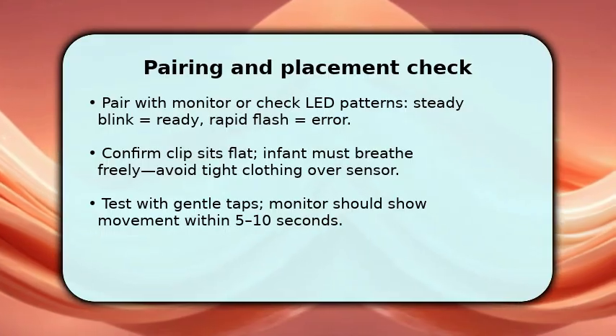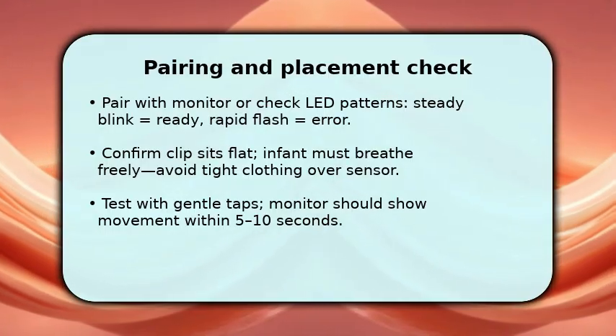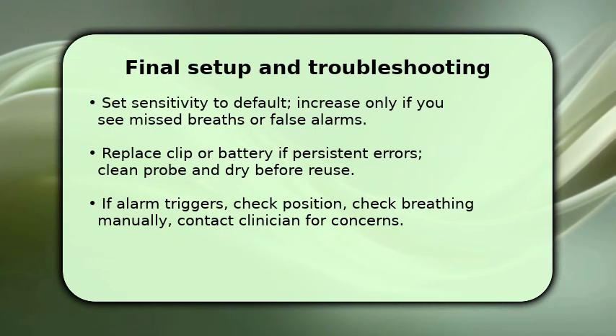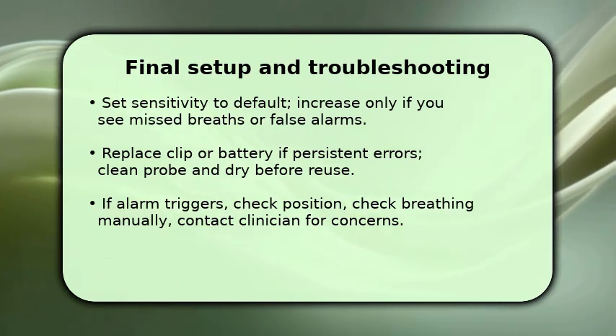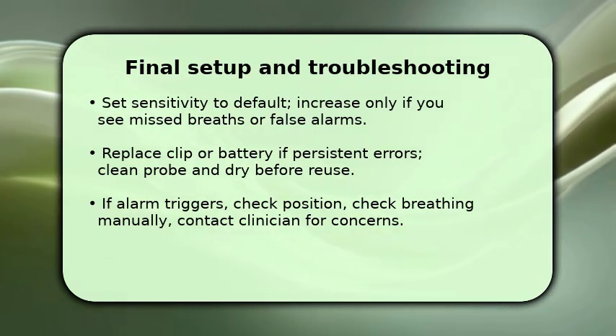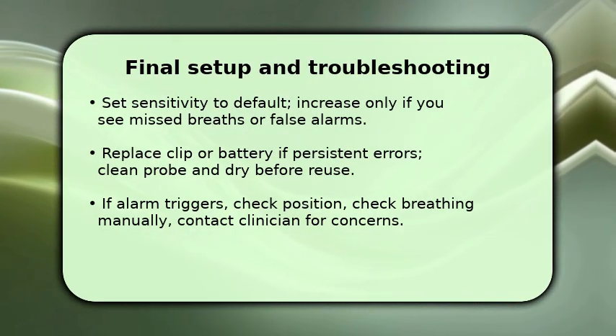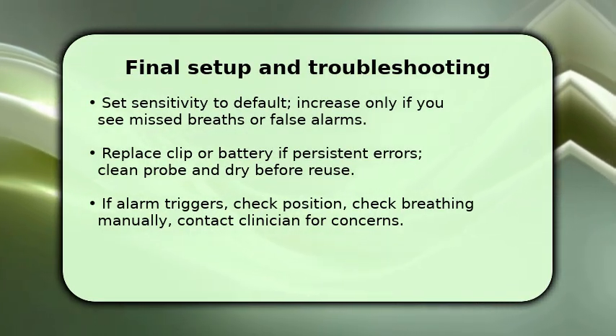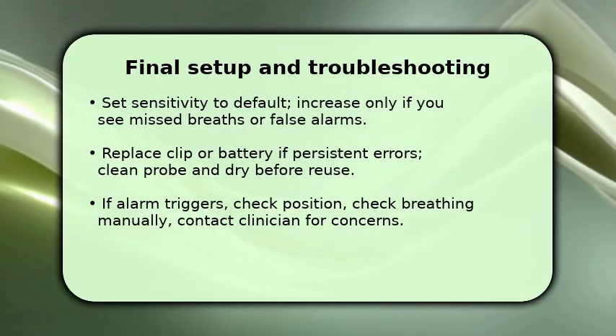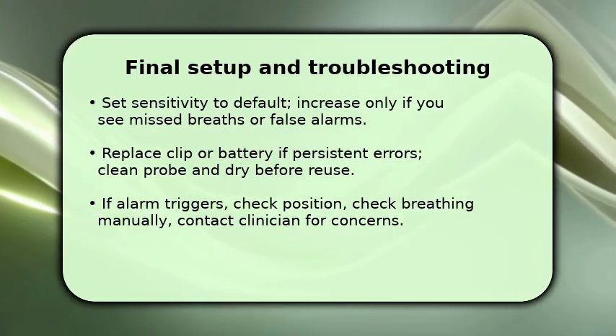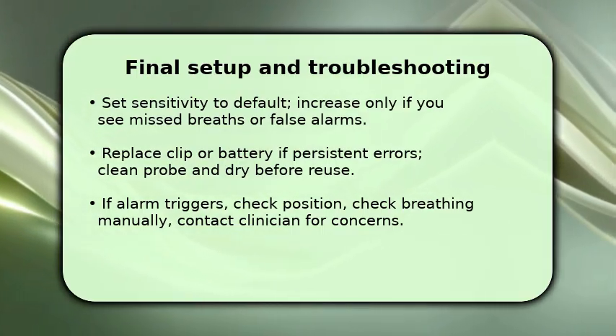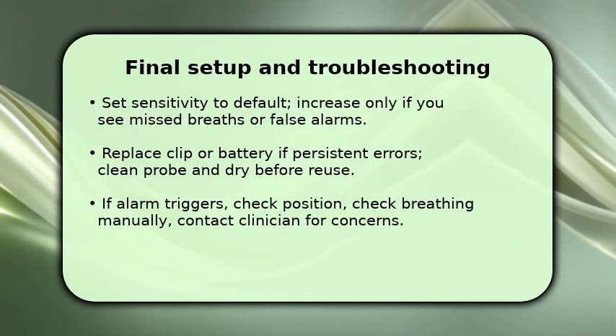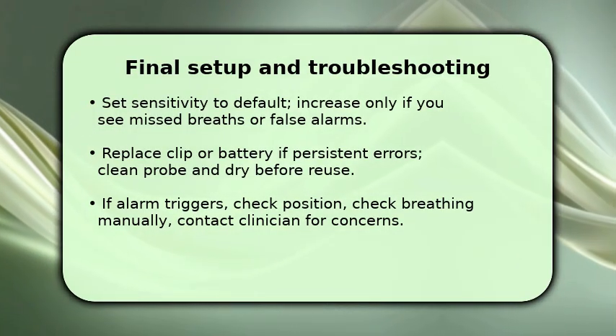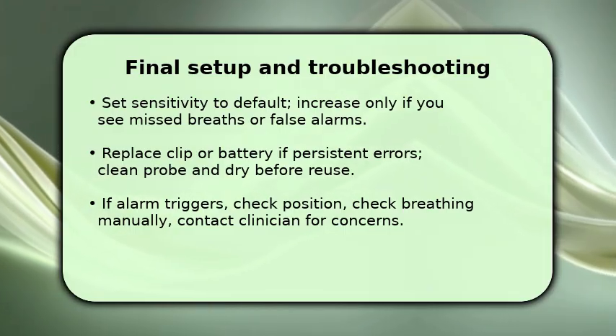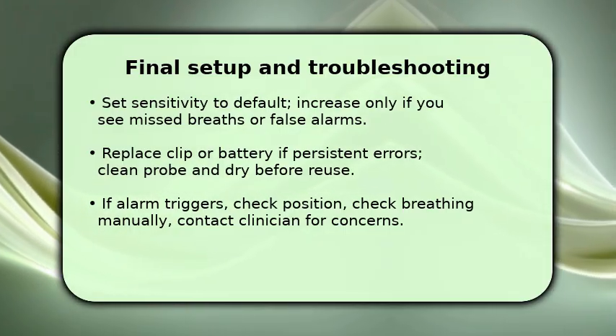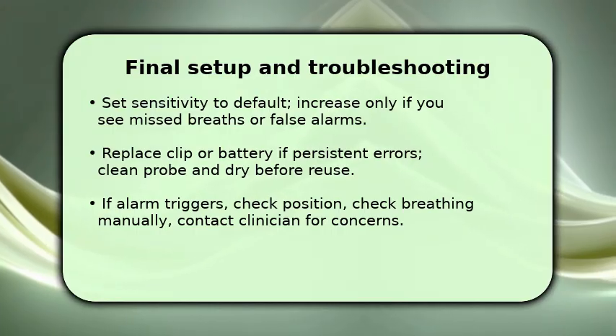You finish by customizing sensitivity and knowing a key troubleshooting step. Start with the manufacturer's default sensitivity because it balances detection versus false alarms. Only increase sensitivity if you observe missed breaths, or lower it if false alarms occur. If errors persist, replace the clip or battery and clean the probe, drying thoroughly before reuse to avoid corrosion. If an alarm triggers, immediately check the clip position and assess breathing manually. If you remain uncertain about the infant's condition.